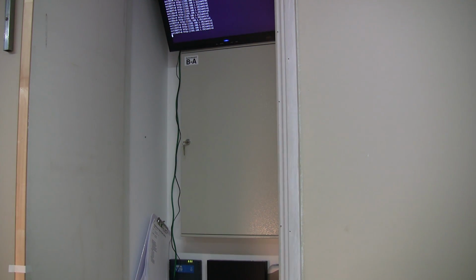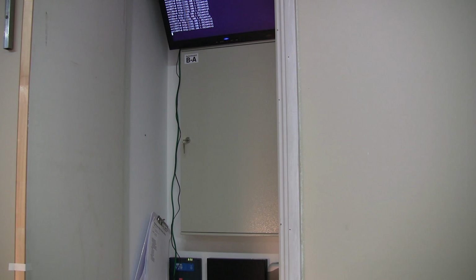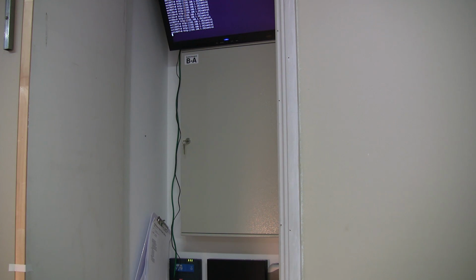Just below that is the automation switchboard, which we'll look at in detail in a moment. You'll see it's marked BA, part of the labeling scheme here: B is the identifier for the telecommunications space, switchboard A in space B. There's a hierarchical naming scheme going from the telecommunications space down to items within it, and then to individual channels, circuits and cables. The idea is you can grab any cable and know exactly where it's terminated at both ends.